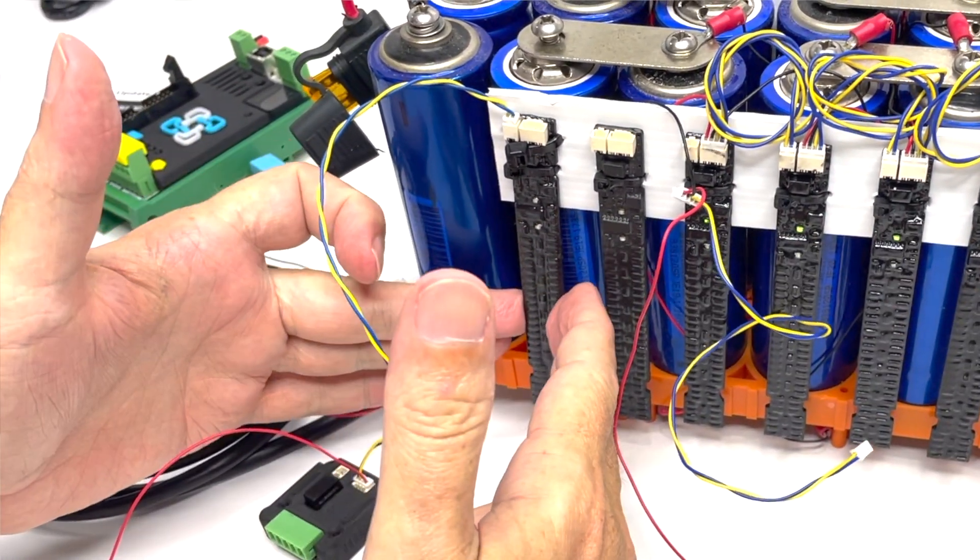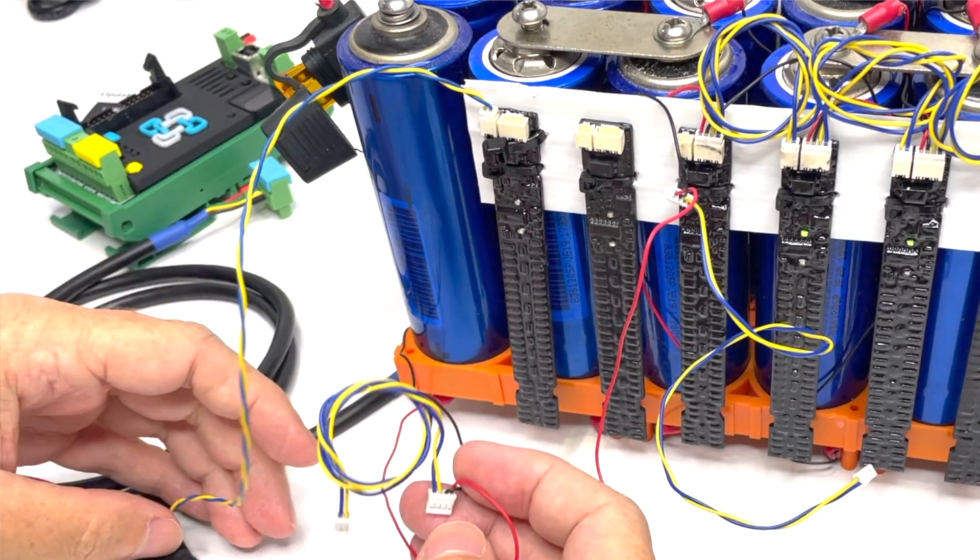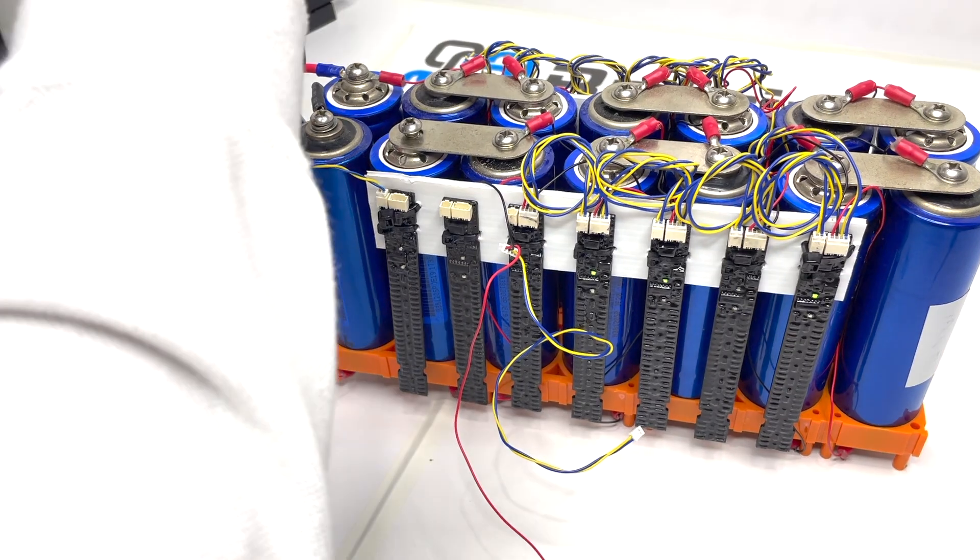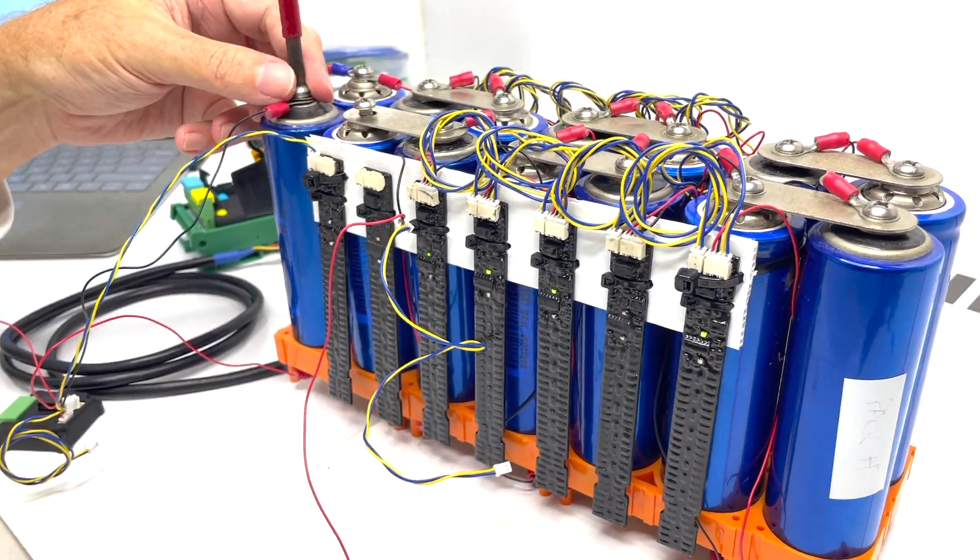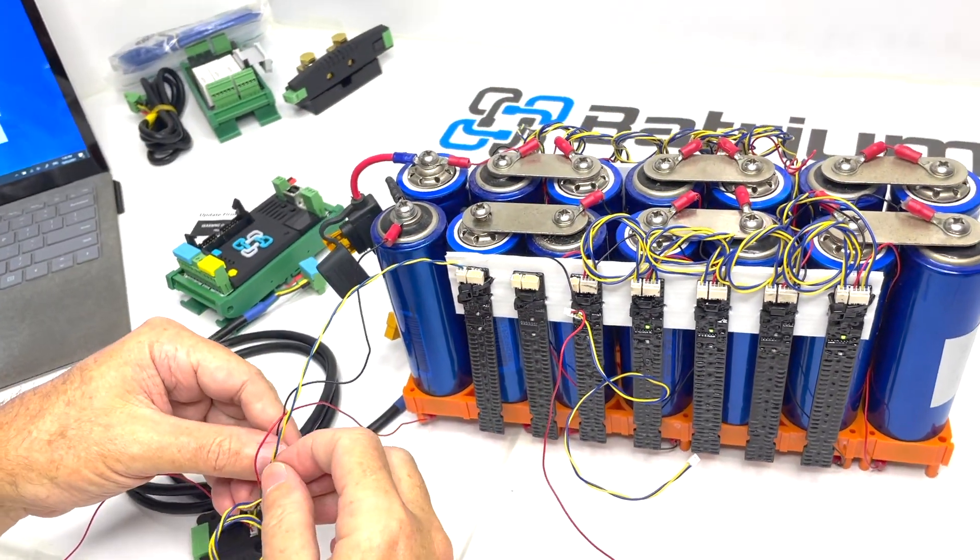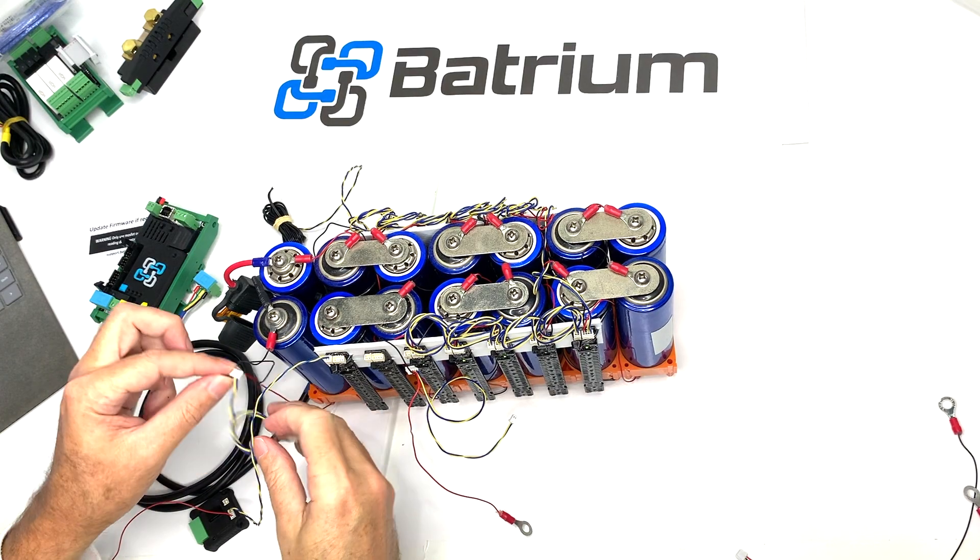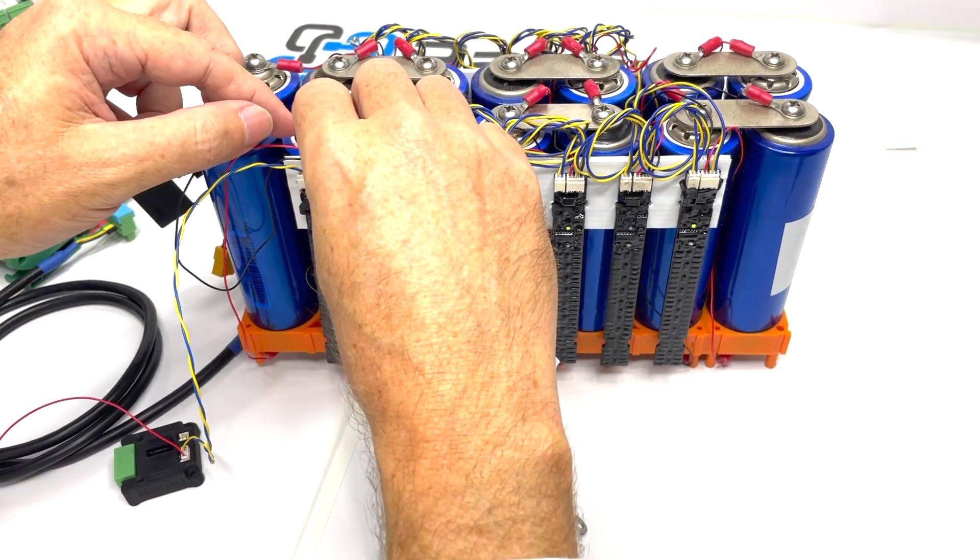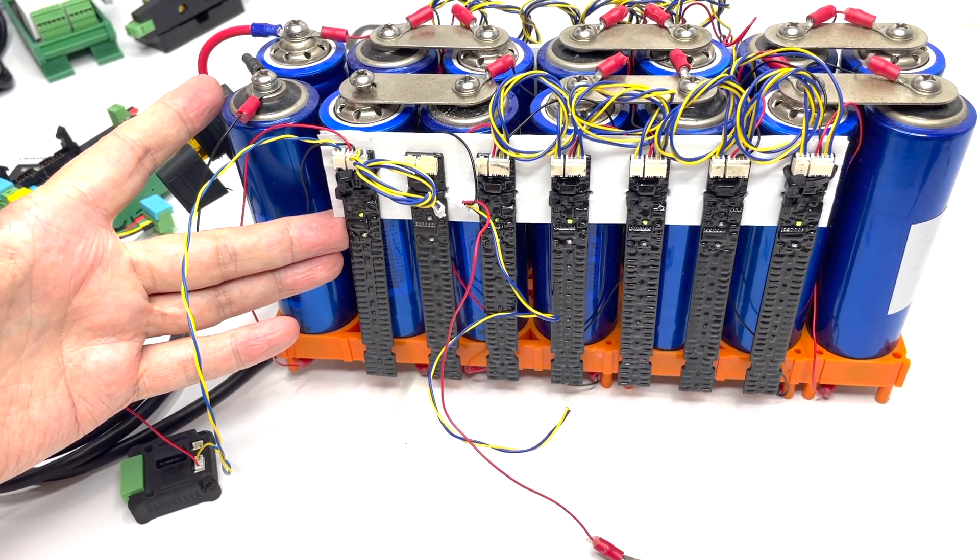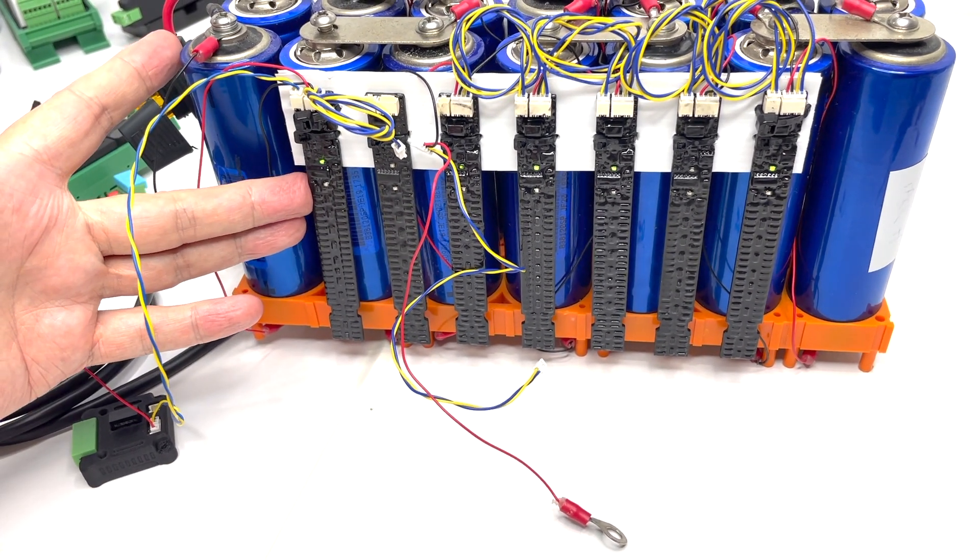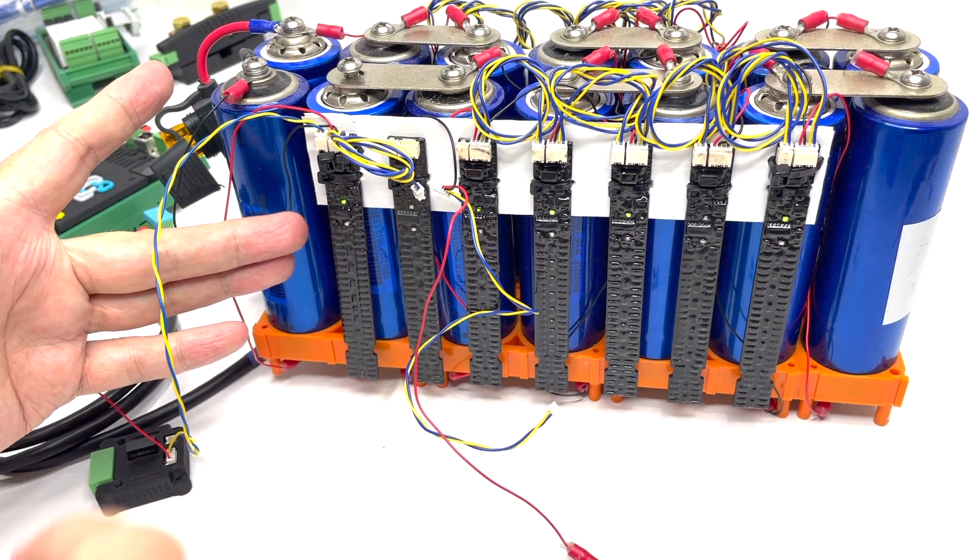Now from this device we're going to continue the process. So we're starting here with this first cell. So I take a cable such as this one and we always connect both ends. So in this case I'm going to take out the wire and attach it. Now because we've got good proximity we're using small wires so we don't have to add an inline fuse. Otherwise if we're extending it away we should be adding fusing. So in this case I'm bringing the wire up and connecting it to the four pin. So we've come from the IsoMon across and up and now we're tagging the four pin plug in. And this here joins our first mon. In this case you will see that it actually had both lights flash for a momentary period of time and then the red light goes out. And that just confirms for the first four hours you plug this in the green LED is on just to confirm that it's been powered up. Hasn't been commissioned yet but it's just been powered up.